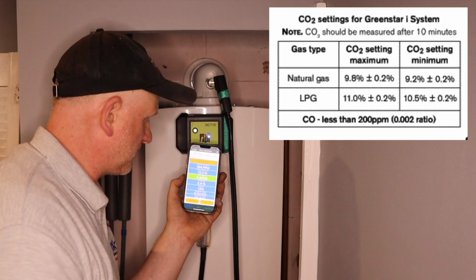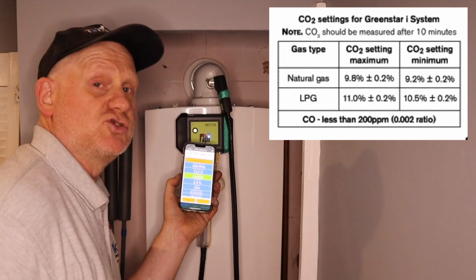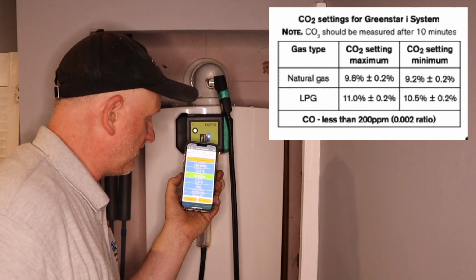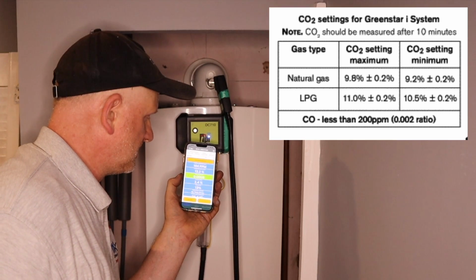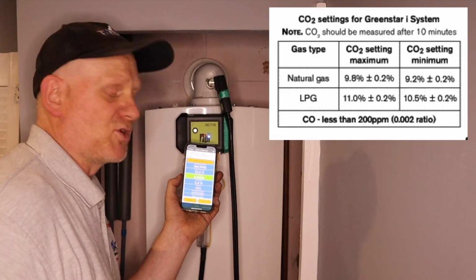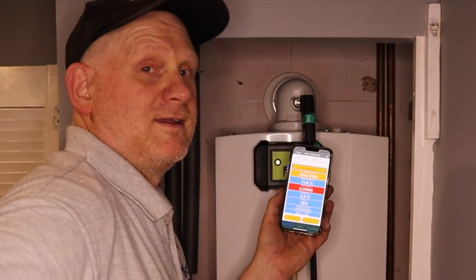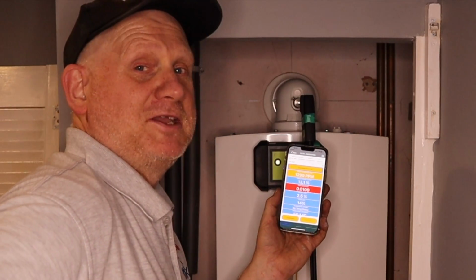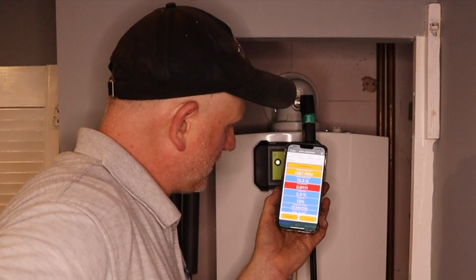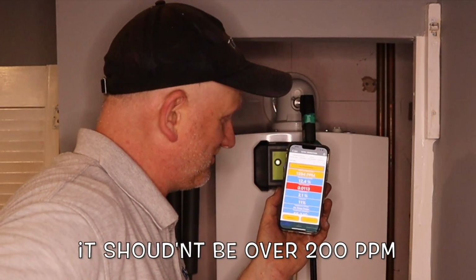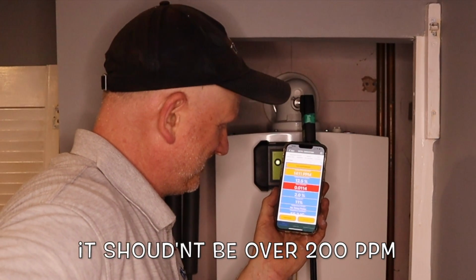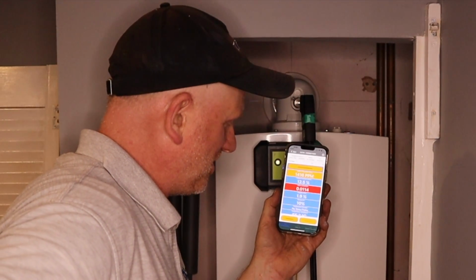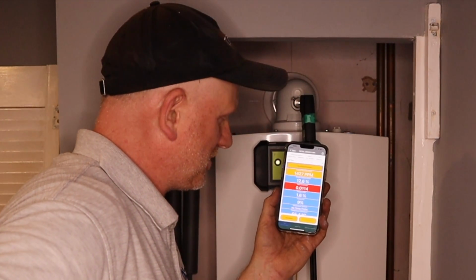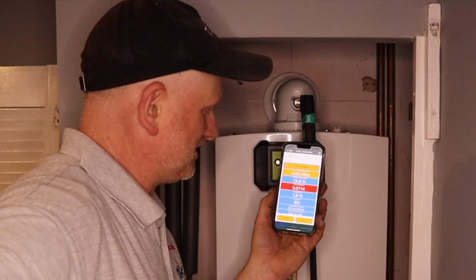Okay, now remember this is an LPG boiler, so we need to look on the chart to see what our minimum and maximum CO2 should be, but at the moment it's 12.2%. Okay, so now we need to put it in maximum. So we're on maximum and it's not looking good, is it? 1,361 parts per million for CO and a ratio of 0.0113 with 12.6 CO2.